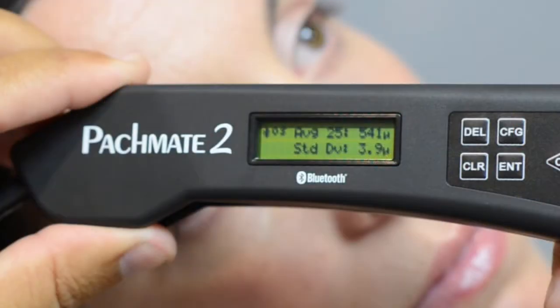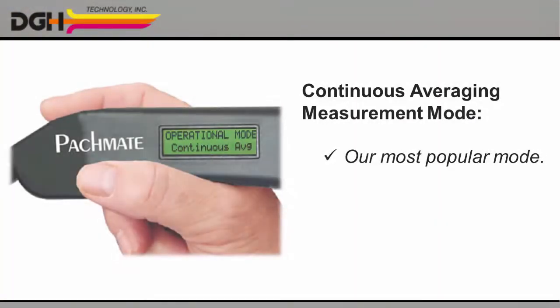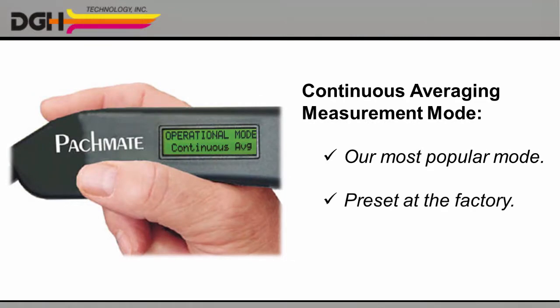The unit then automatically displays the average of all the measurements, as well as the standard deviation. This is how most technicians use our pachymeter, and it's also how we ship the unit from the factory. So, if continuous averaging is what you need, you'll be ready to start right out of the box.